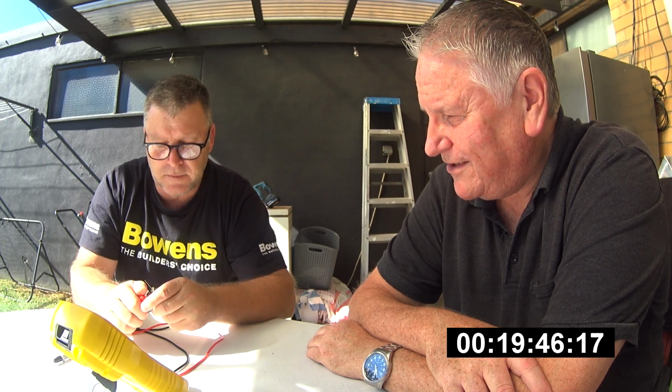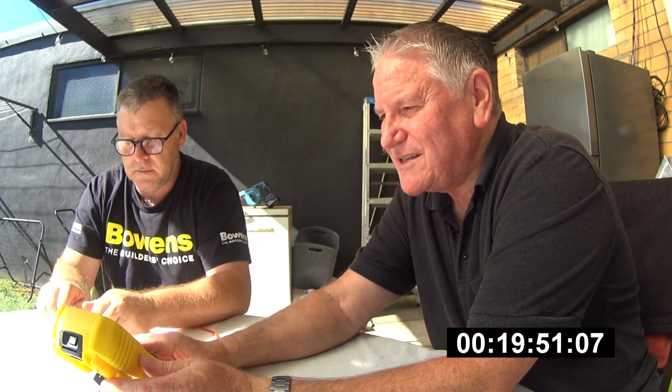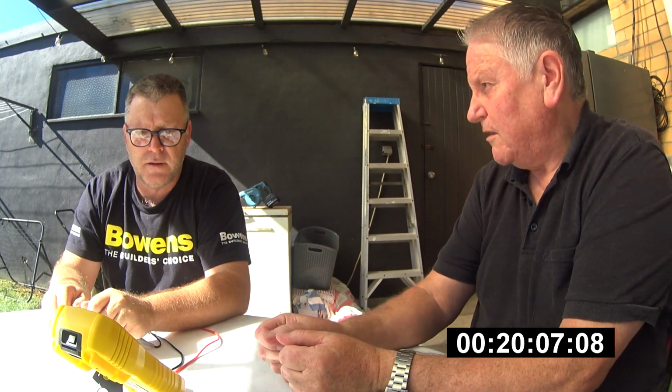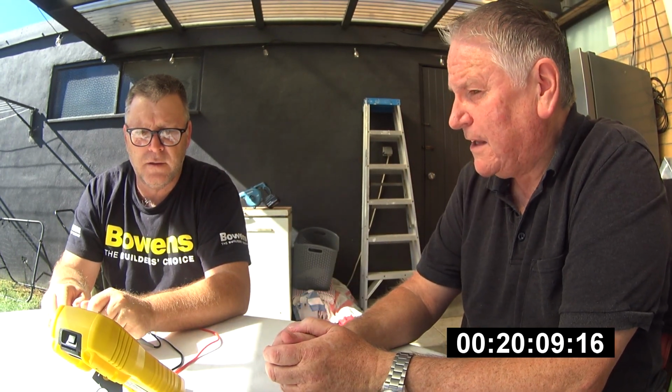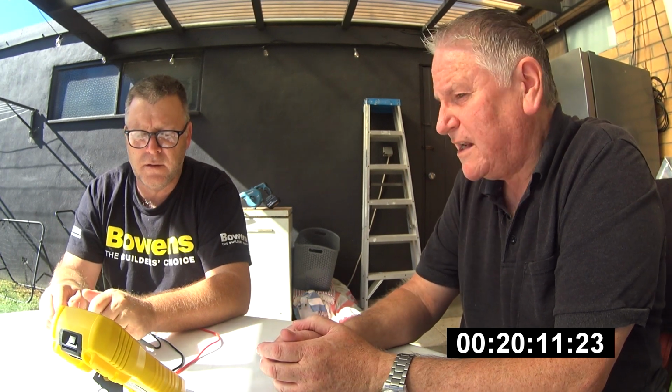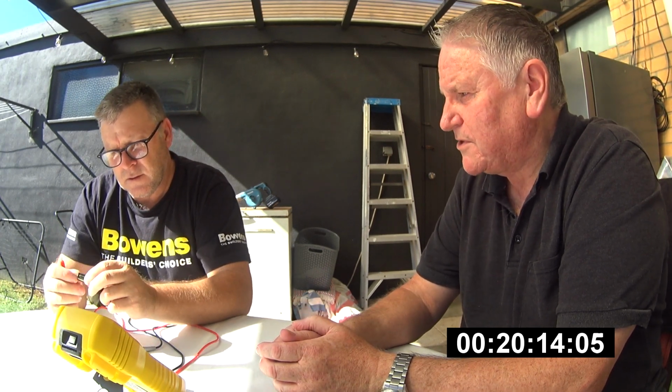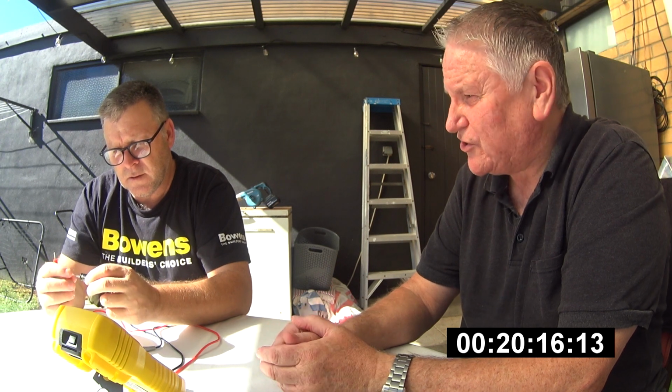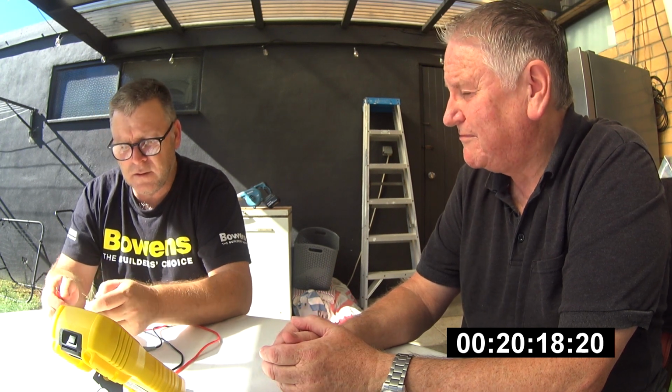Can I do something like this? You can do that. All right, we'll watch the display. See it rising? Yes. Okay. So we know that that capacitor is doing what it's supposed to do. It's working. Does it get to its full value? We don't know until we actually take it out and test it. But 9 times out of 10, pop the probes across the capacitor. If it starts to charge up like that, it's pretty good.